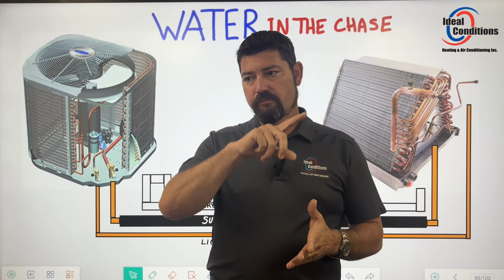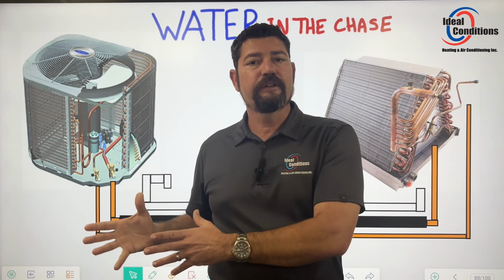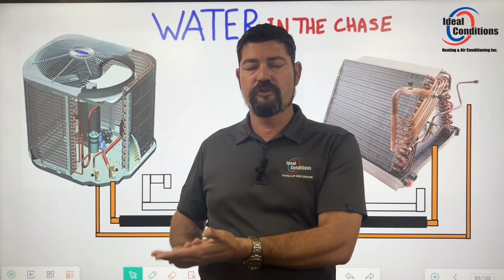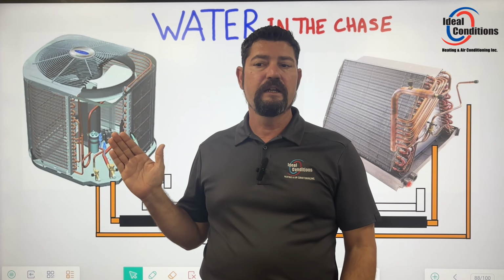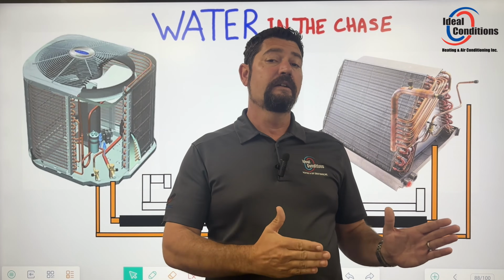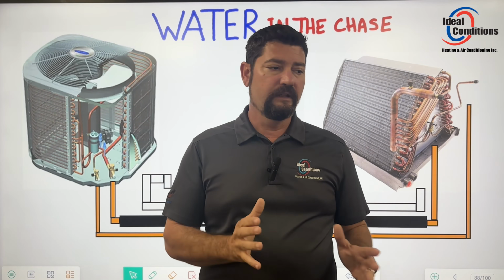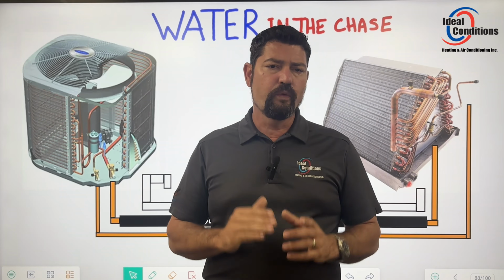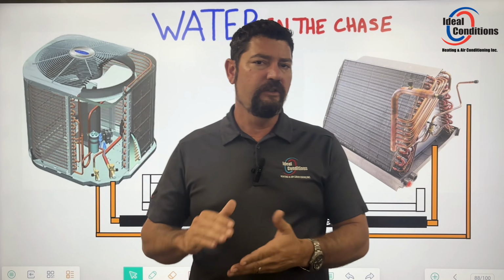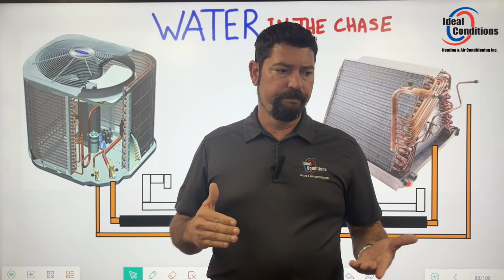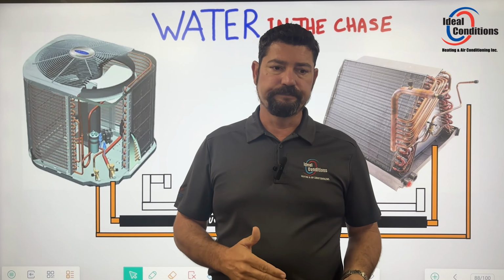Your compressor is going to love it. It's not going to really care. The pressures aren't going to change, but your superheat's going to be extremely high, and you're guaranteed to return in a vapor state. So that's not bad. But what if you were looking for superheat and you saw a 35-degree superheat? You're going to go, oh my gosh, there's a problem here.